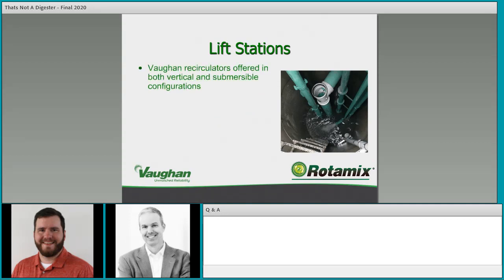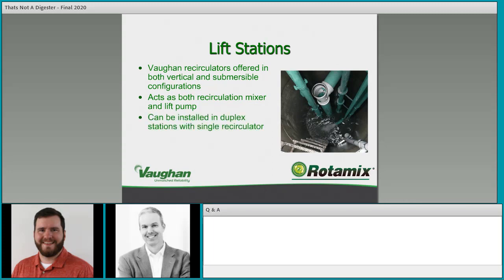For smaller stations, Vaughan recirculators are offered in both vertical and submersible configurations. These can be used for small and drop-in stations with a reliable application — acting as both the recirculation mixer and the lift pump. You can provide a cycle of recirculation mixing to agitate and bring everything into suspension, then switch to pump-out as normal lift station operation. It can be installed as a duplex station with a single recirculator for redundancy.